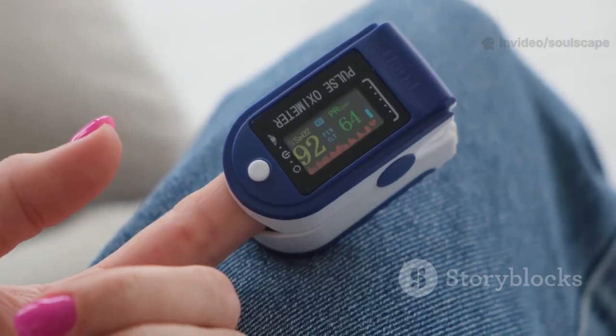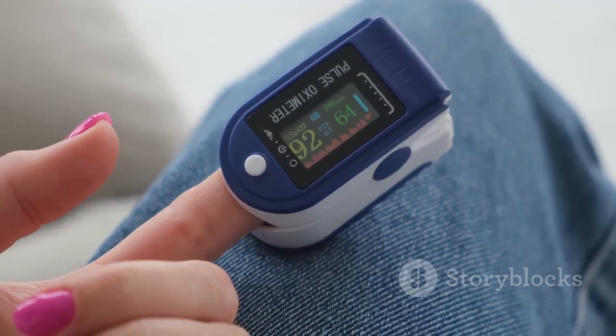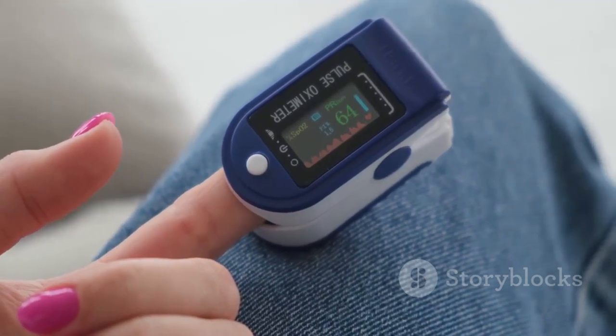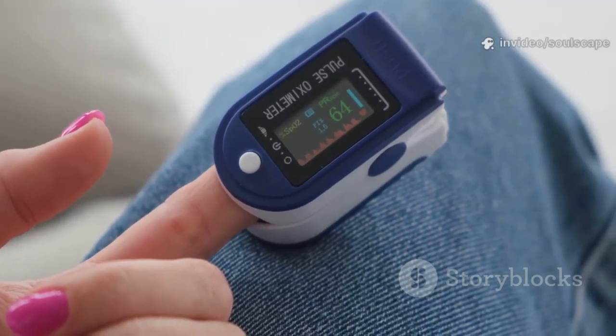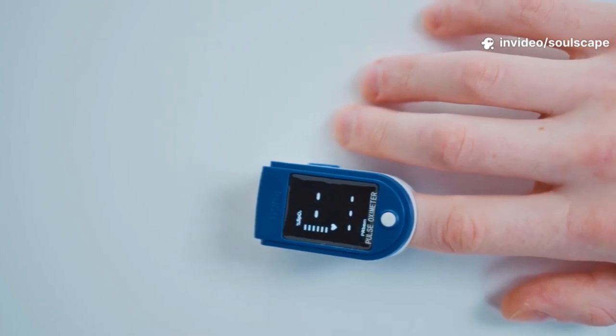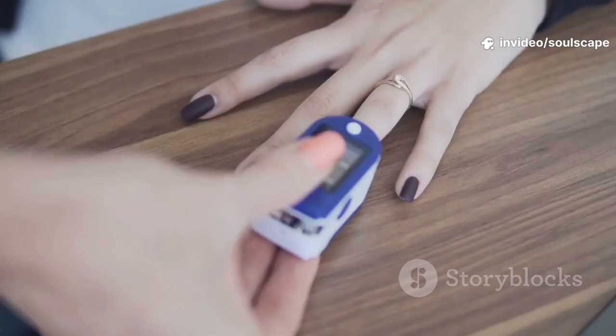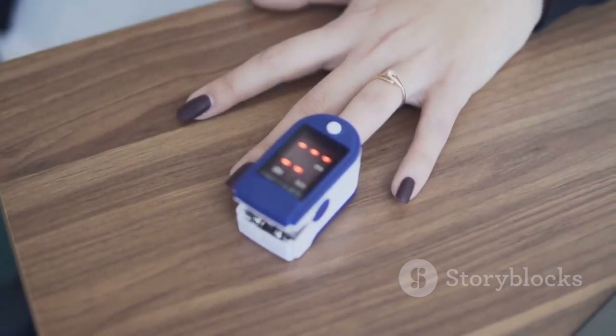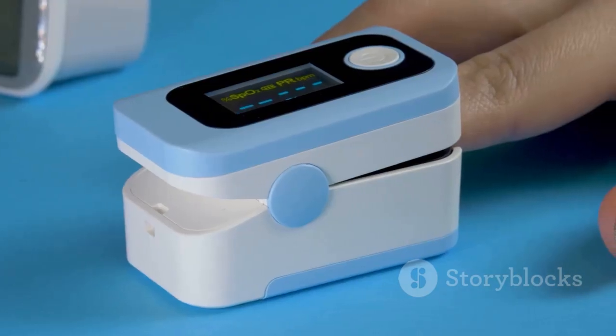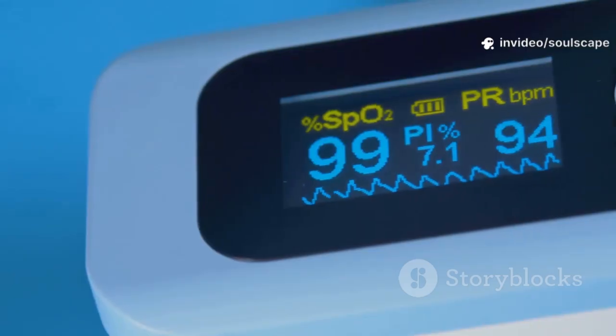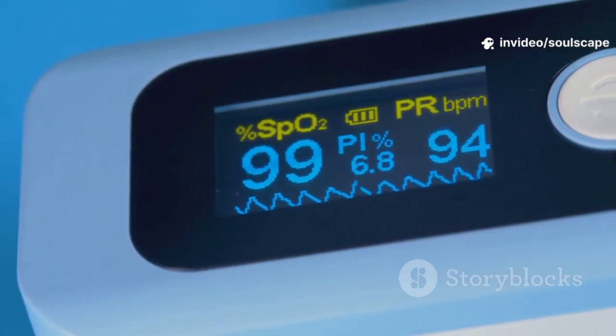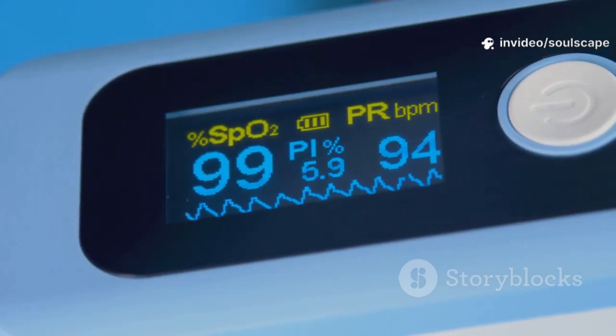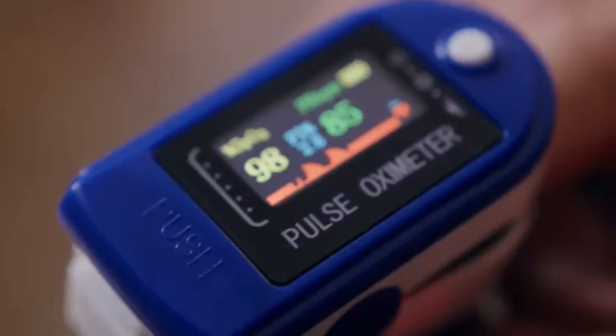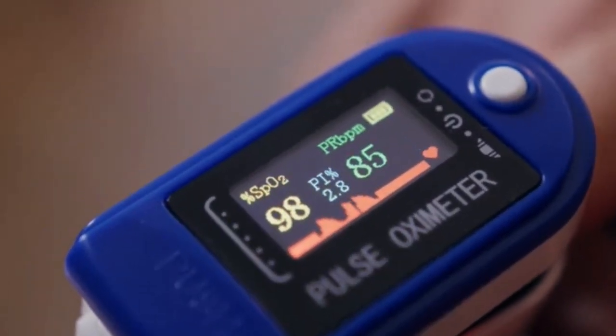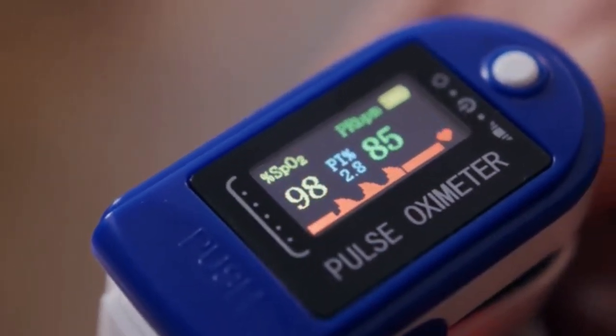Now here's where it gets a little sciencey, but stick with me. Inside that tiny probe are two LEDs. One shines red light and the other infrared. There's also a photodetector that checks how much light actually makes it through the tissue. Why two colors of light? Well, oxygen-rich hemoglobin, or oxyhemoglobin, absorbs more infrared light, while deoxygenated hemoglobin absorbs more red. The device's microprocessor crunches the numbers, compares the absorption, and gives you a readout of the oxygen saturation. That's SpO₂. Usually we want that number between 95 and 100% in healthy people.